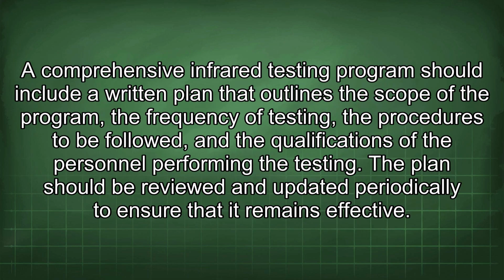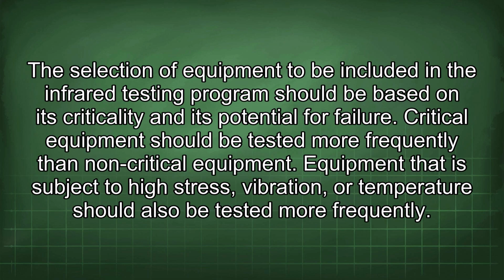A comprehensive infrared testing program should include a written plan that outlines the scope of the program, the frequency of testing, the procedures to be followed, and the qualifications of the personnel performing the testing. The plan should be reviewed and updated periodically to ensure that it remains effective. The selection of equipment to be included in the infrared testing program should be based on its criticality and its potential for failure. Critical equipment should be tested more frequently than non-critical equipment. Equipment that is subject to high stress, vibration, or temperature should also be tested more frequently.